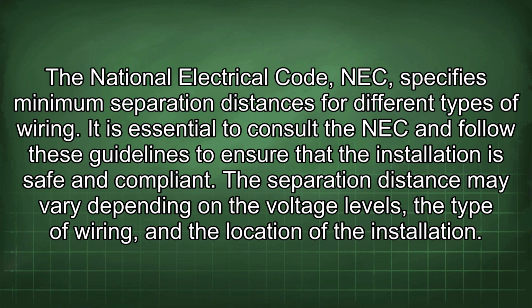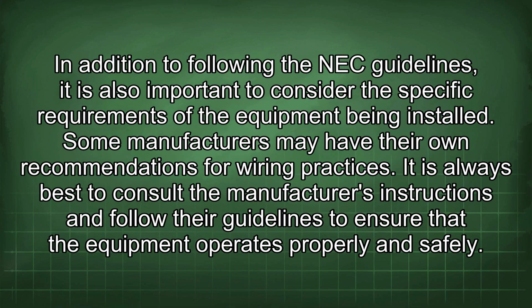It is essential to consult the NEC and follow these guidelines to ensure that the installation is safe and compliant. The separation distance may vary depending on the voltage levels, the type of wiring, and the location of the installation. In addition to following the NEC guidelines, it is also important to consider the specific requirements of the equipment being installed. Some manufacturers may have their own recommendations for wiring practices.